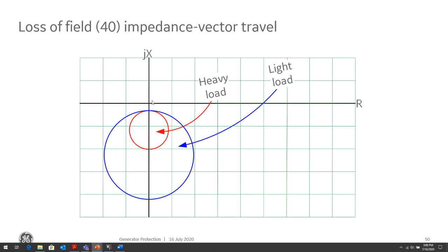Whereas in the inner circle, we want a limited delay, not instantaneous. And the only thing we really need to coordinate there with is maybe if we have a voltage fuse failure, voltage transformer detection, then we might want to be able to coordinate with that. So if there is a blown fuse or a loss of an MCB, be able to detect that condition and block that element.